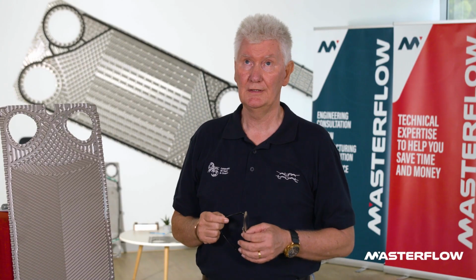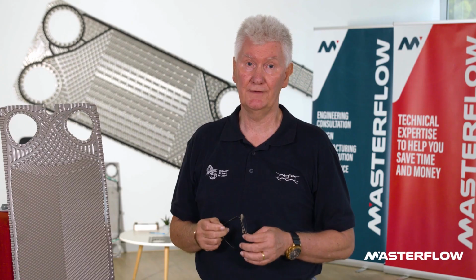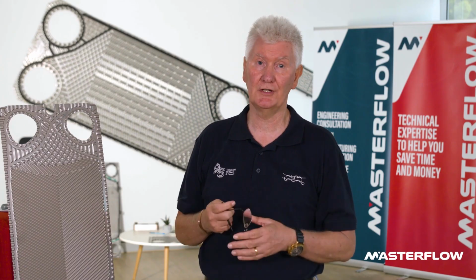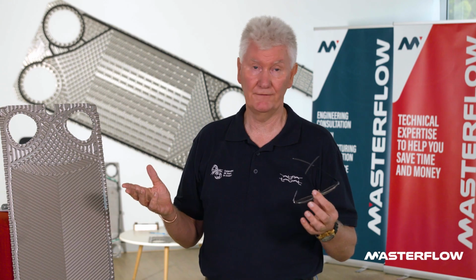Most common is pressure spikes. They've hit the exchanger with 20-30 bar pressure. They've popped out a gasket. It can be fixed relatively easily on site.